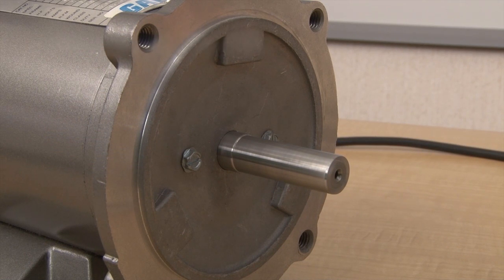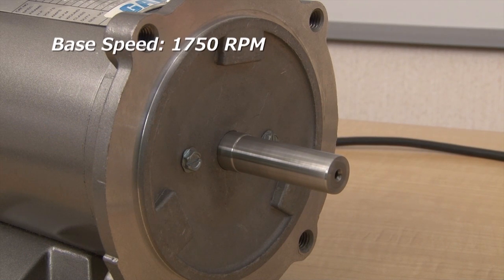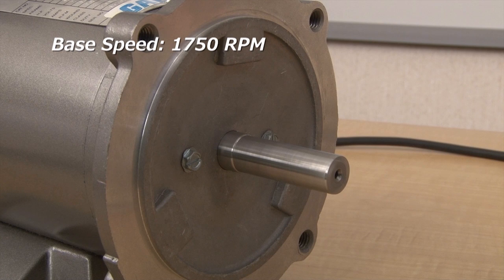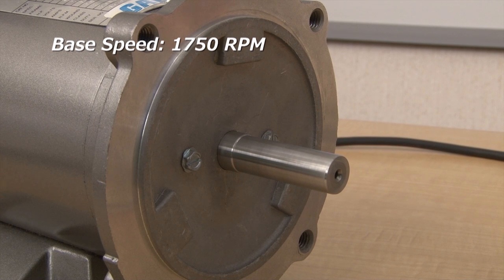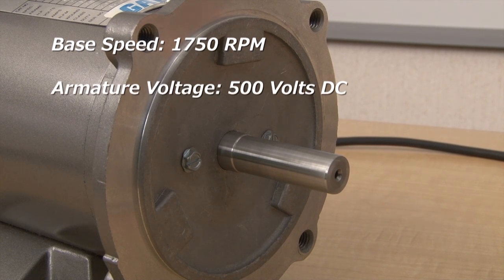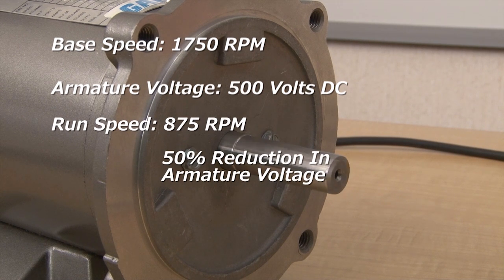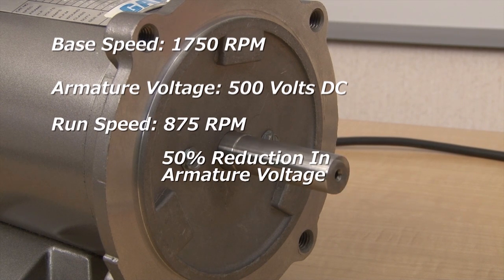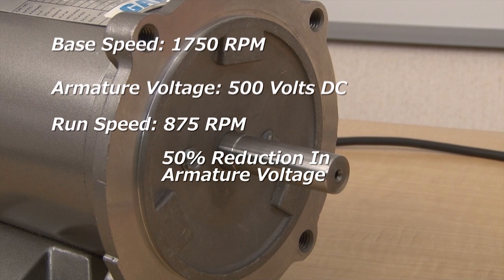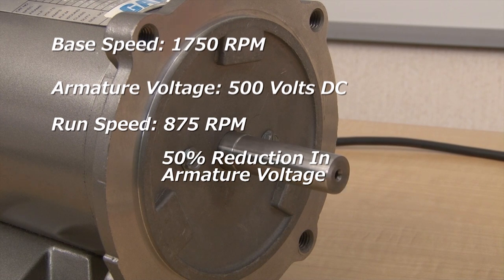For example, a motor with a base speed of 1750 RPM and an armature voltage of 500 volts direct current will run at 875 RPM with a 50% reduction in armature voltage.